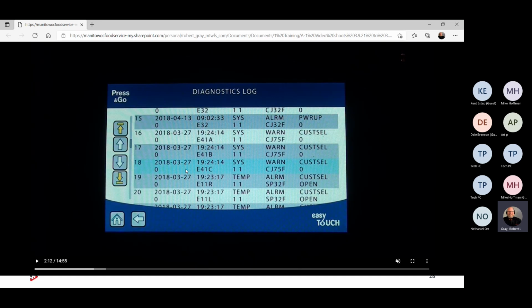But let's say you're on the right, the middle, or the left lane, and you have a 41A, B, and C. I'll show you in the wire diagram: through the grill contactor, or the control contactor, it goes through the power switch, engages that contactor, and goes to a jumper, basically sending power to each lane. One leg of power goes to the AC to DC power conversion board. The other leg goes up through my safety thermostats for each heating zone of that lane and back down to energize the coil of the load contactor, sending the 3-phase power down to the solid state relay board. That board communicates to the SIB that we have the appropriate voltage, and it communicates it up to the UI so you can get the visual you're seeing here.